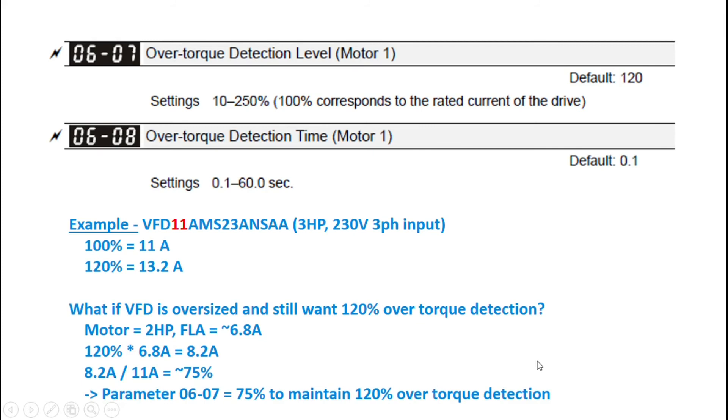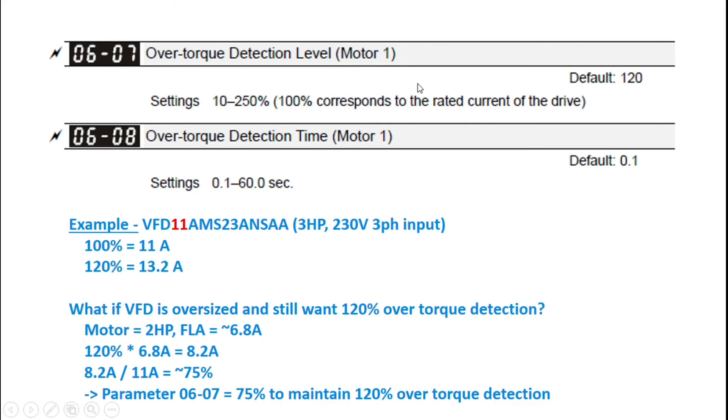And then the last parameter here is your 0608, which is your over torque detection time. And that just says you're defining the time that you can be at or above your over torque detection level before you're going to trip, or fault, or warn. Do whatever your action is in parameter 0606.